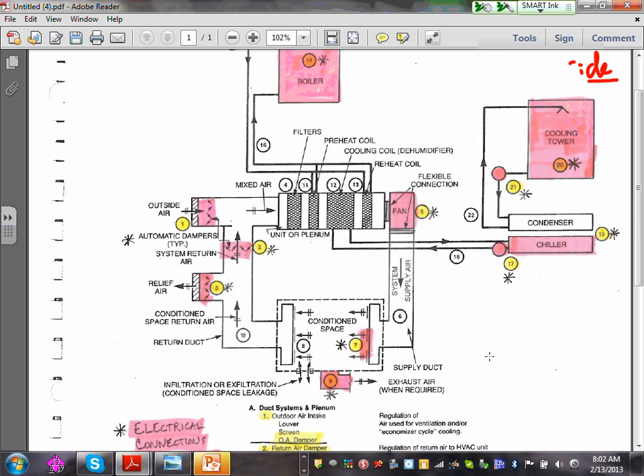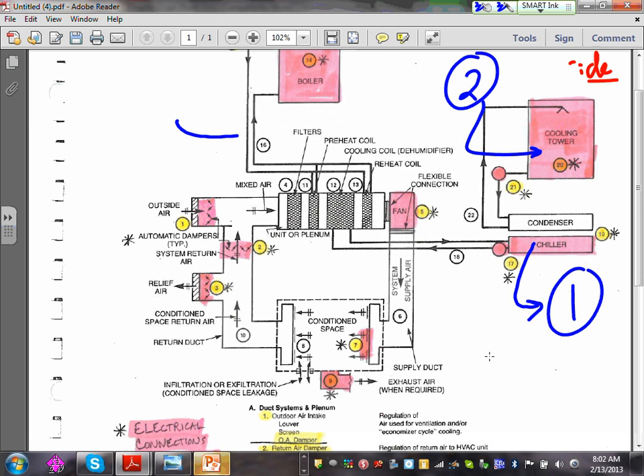So what do you need to do? Here's where you come into this picture. You need to provide a circuit. Here's circuit number 1 for the chiller. For the cooling tower, circuit number 2. Circuit number 3 for the boiler. Then your air handling unit, typically you have circuit number 4 for the air handling unit, and sometimes they also have a fan. It is number 5.